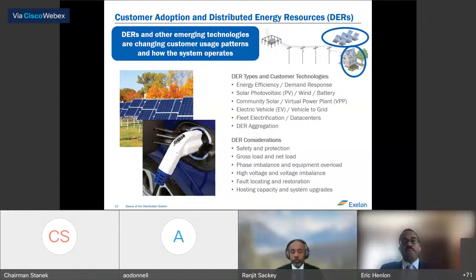DERs also provide some impact on the voltage, as Ranjit shared earlier, since the utility is responsible for maintaining certain voltage levels to our customers. With the DERs on the system, the technical aspects of how they operate create certain impacts on the voltage, creating voltage imbalance and high voltage, which we have to study and make sure the system is adequately engineered and operated so that we maintain those voltage tolerances on the system.